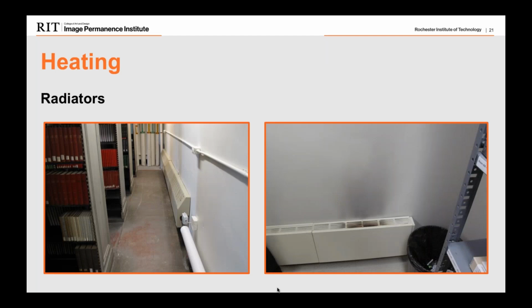The last item I'll discuss for mechanical systems is the standalone radiators. Some of you, these may be all you have in your collection space. Not all of us have HVAC systems; you may just have these radiators. They're designed to what we call wash outside walls or window surfaces with warm air. They come in two styles, either water or electric. You can identify if it's water, most likely it will have steam or water pipes going directly to it, or if it's electric, it will have an electric line going to it. And I was asked to identify that this black mark you see above this heater is actually from the operation of the object. The heater was firing much hotter than it should have been, not to the point of causing a fire, but to the point of leaving black marks along the walls and on the unit.